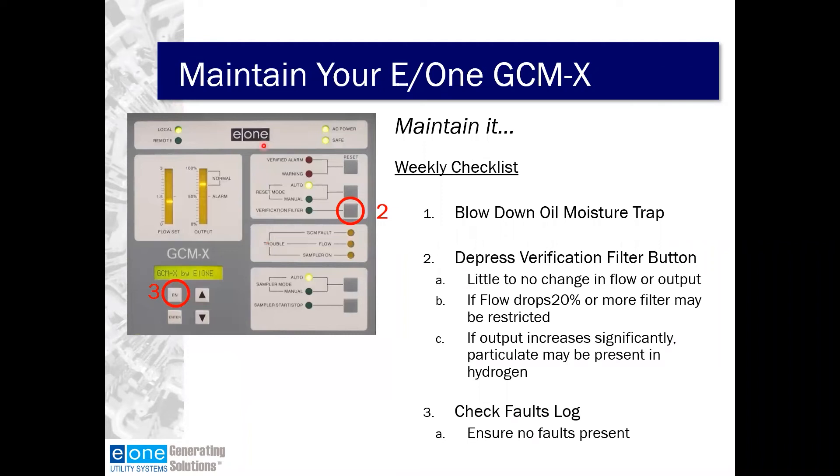Also on the weekly checklist, depress the verification filter button — there should be little to no change in flow or output. If the flow drops by 20% or more, the filter may be restricted. If the output increases significantly, particulate may be present in your hydrogen — consult with your E/One service technicians. Also check the fault log, ensuring no faults are present, as covered in Chad's video.